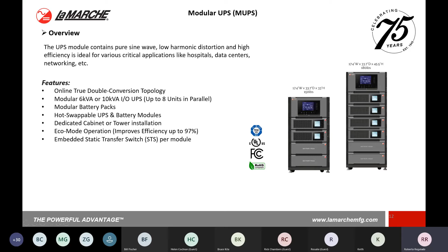And then I want to show you here the cabinetized solution. So when you are running, you do have a couple different options as far as the housing that you want to use. So you have your pre-configured enclosures, which allow for, you can see here, the 6-slot enclosure, a 4-slot enclosure, and we also have a customized setup that we can actually accommodate. So this one here, we do have various slots, various sizes. So this is actually a 42 RU cabinet, and we can actually allow for 8 modules, power modules, and then for the rest, or obviously different number, but the rest can be battery packs as well.